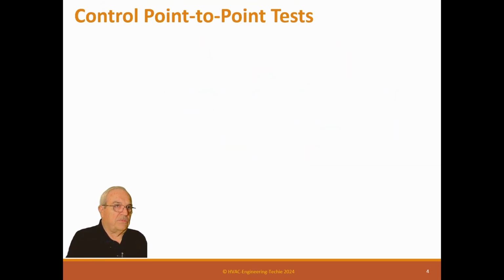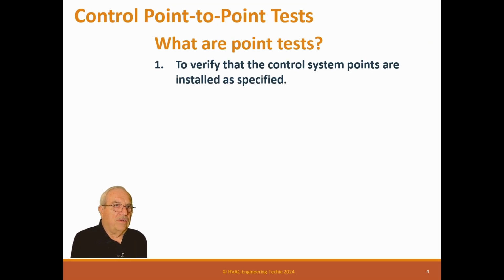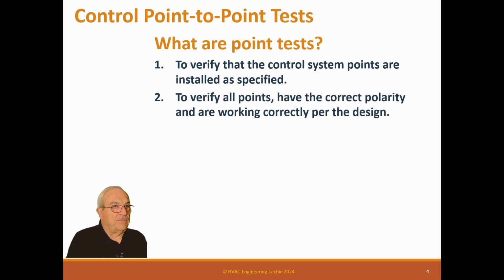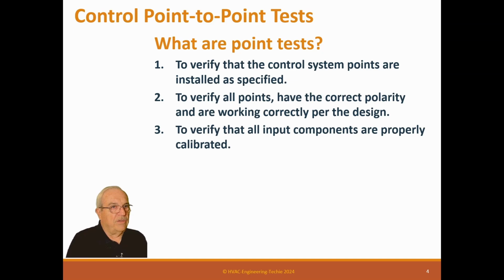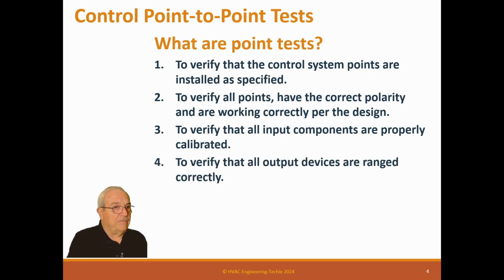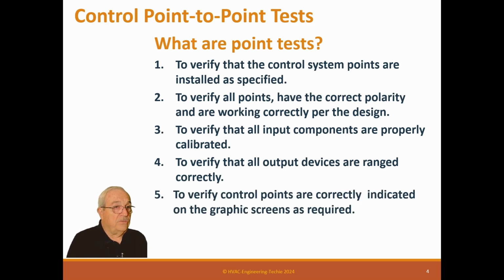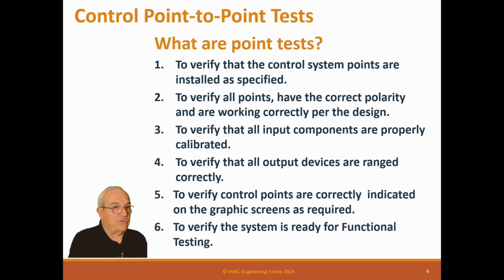So this is the test we do. What are point tests? To verify the control system points are installed as specified. To verify all points have the correct polarity, meaning they open when they open and close when they close, and are working correctly per the design. To verify that all input components are properly calibrated. To verify that all output devices are ranged correctly. It's part of the process we need to do. To verify control points are correctly indicated on the graphic screen as required. This is why we do it from the graphic screen to the field. No matter how many interactions it goes through, those are the two points we want to make sure are the same. To verify the system is ready for functional testing.